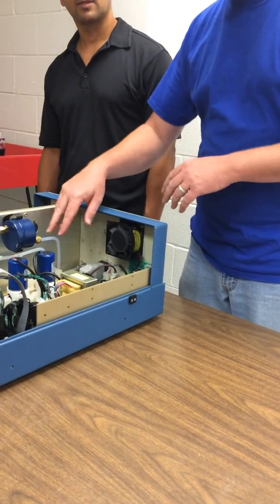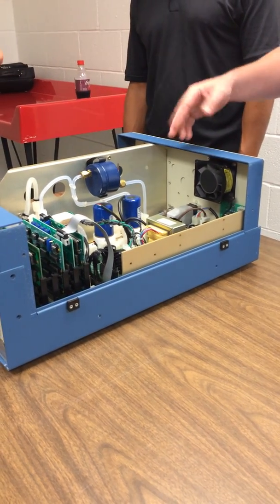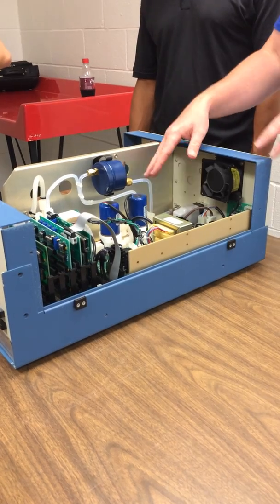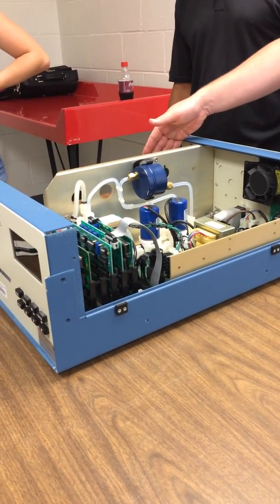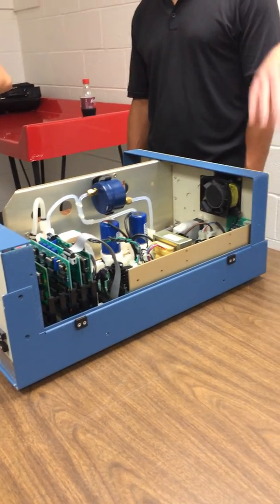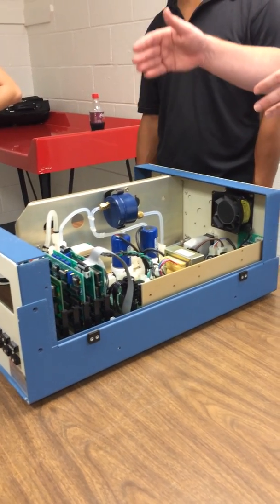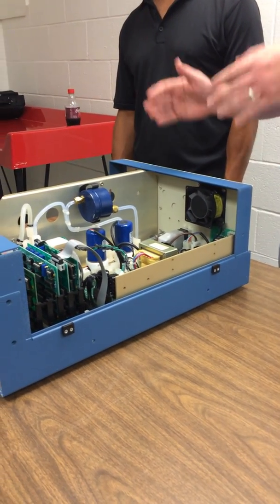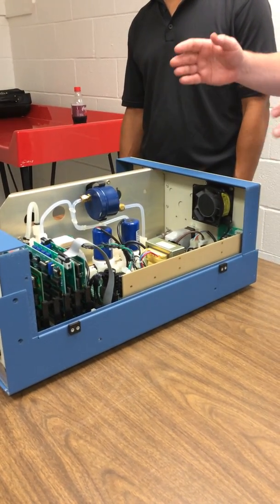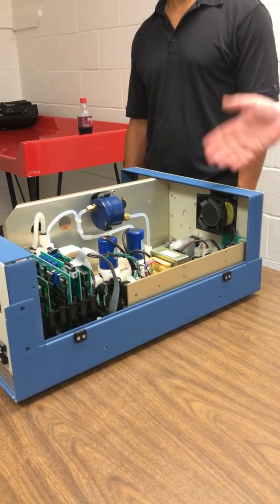So the air comes in through these valves. It gets split between 2 flow paths. This is the ozone, and that's the CO. So for the ozone, one path goes straight into the cell. The other path gets routed through this scrubber, which selectively removes the ozone. So one cell is measuring the absorption from ozone plus all the other absorbers. The other cell is measuring the absorption from all the other absorbers. So the difference is ozone.